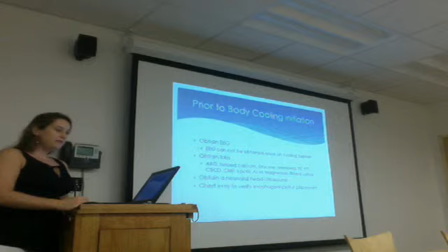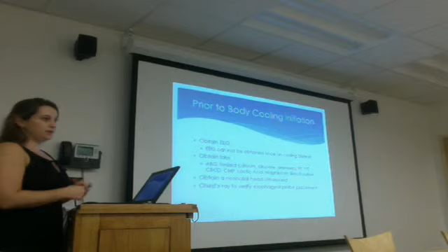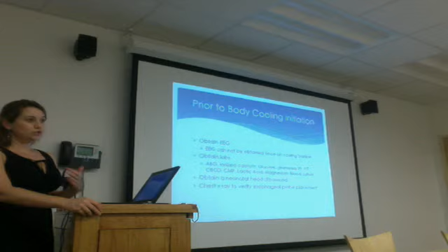Before we put the baby on the blanket, we need to obtain our EEG. The EEG machine will not pick up if the baby is already on the cooling blanket. There's too much artifact and it does not pick up. So just keep that in mind. We're going to obtain our normal labs. We're going to obtain a head ultrasound. And we're going to get a chest x-ray to verify that our esophageal probe is truly at the core where we want it.